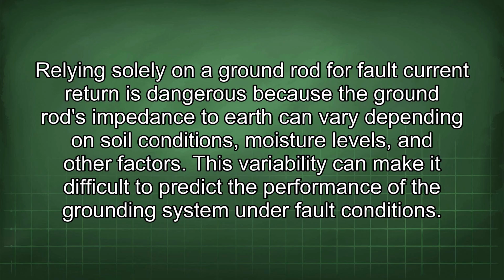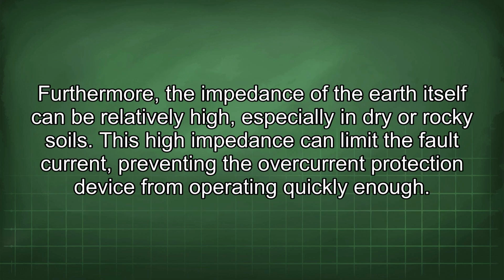Relying solely on a ground rod for fault current return is dangerous because the ground rod's impedance to earth can vary depending on soil conditions, moisture levels, and other factors. This variability can make it difficult to predict the performance of the grounding system under fault conditions. Furthermore, the impedance of the earth itself can be relatively high, especially in dry or rocky soils. This high impedance can limit the fault current, preventing the overcurrent protection device from operating quickly enough.